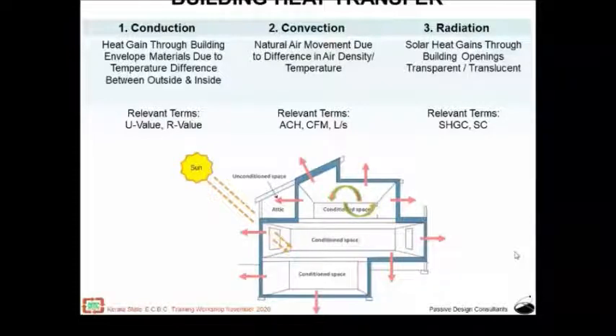The third mode, which is radiation, is heat gain through radiation in buildings from transparent and translucent building openings like windows, skylights, etc. The sun with its direct light will lead to significant heat gain. There is also indirect radiation heat gain, which is from the different paved or construction materials around your building, which absorb solar heat and re-radiate it inside the building as long wave radiation, infrared radiation. So those radiations, be it directly from the sun or indirectly from the paved surfaces around the building, can be prevented by having good quality solar shades or building shades and designing the exterior surroundings of the building with more greenery.